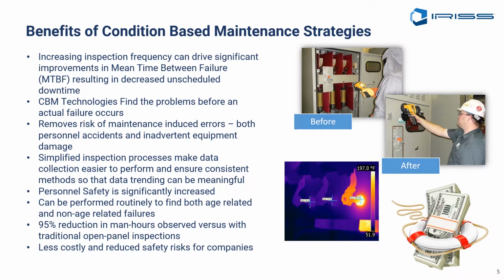So increasing that inspection frequency can drive mean time between failure in the right direction. All these technologies, the idea behind them is to find problems before the failure occurs. That's what all these technologies can do. They get these early warning signs, these early signatures that there's a problem, and allow you to make a decision about corrective action. It removes the possibility of maintenance-induced errors, opening and closing panel doors, torquing connections that don't really need to be torqued and breaking something by accident. All of these kinds of problems can be eliminated by really only performing physical wrench-turn type maintenance when we see something is wrong with the asset.